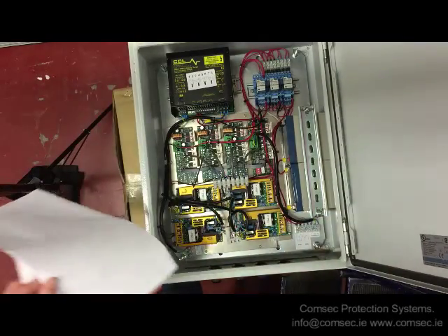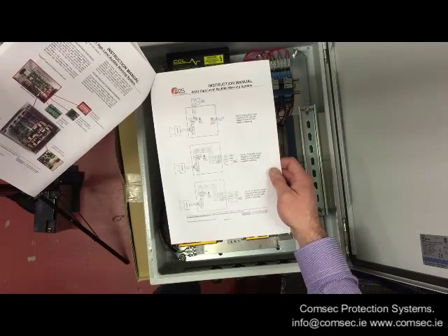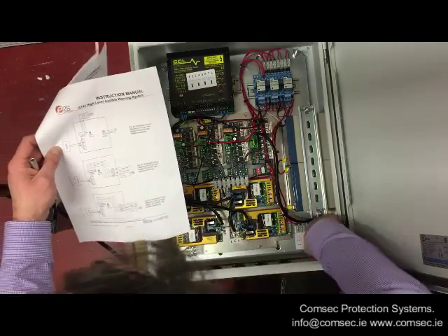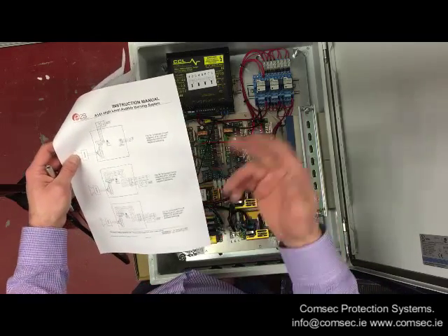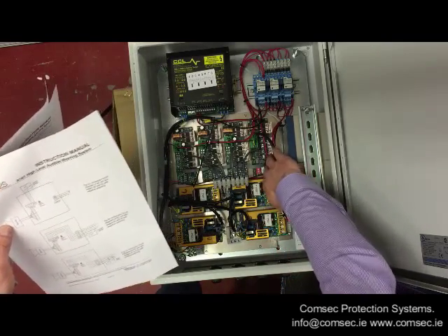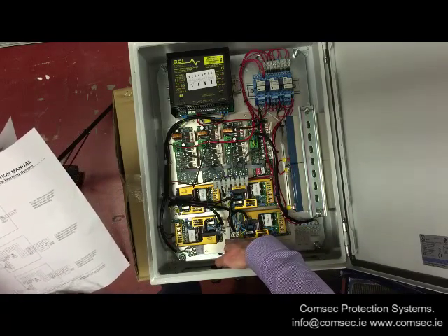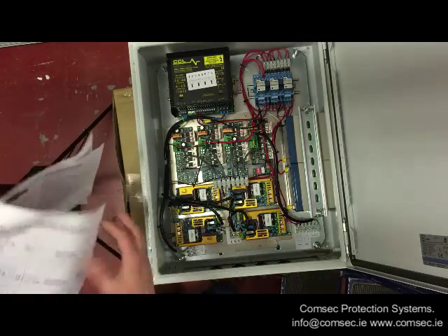There's a mounting guide, and we can send these to you in advance if you want to drill grounds on site for what you're putting up. It's a solid UL-listed box with full connection instructions for your sounders. We have the contactor here for stopping and starting - basically if you're just connecting a switch to this, it's as simple as close the relay, open the relay, and that's your stop/start. Then these are important for your dip connections, and this is your mains input.